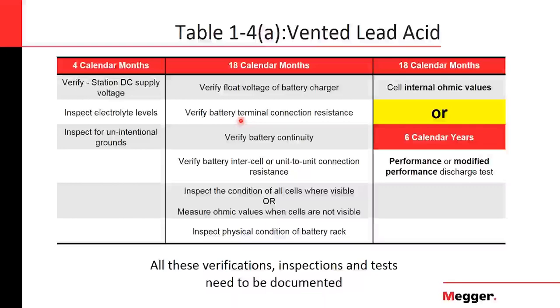And all of this should be documented. It's not just going to the substation and verifying that everything's fine and then you go home. No, you need to document this, and this has to be properly archived and maintained in a database system that you can show whenever NERC comes to do audits, because that's how they will find out if you're following things or not. And audits are the main thing with NERC. They want to see that you are doing the job and that you are maintaining your system. So, 4 calendar months, very basic measurement.